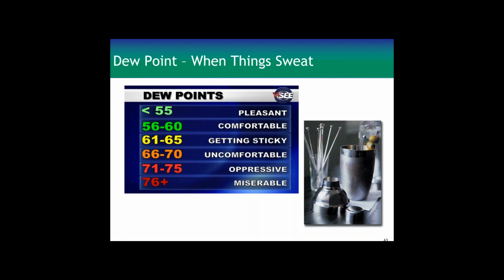We like dew points because dew point is a straight line across the psych chart, and it isn't affected by the temperature of the air as far as the dry bulb temperature, which relative humidity, of course, changes. There's a curved line on the psych chart. So it's much easier to try to control a dew point than a relative humidity, because the relative humidity moves around on the chart, and it may not be uncomfortable. It's easy to say this is.